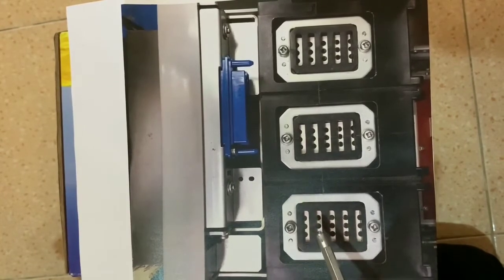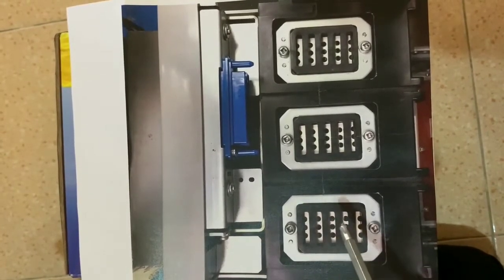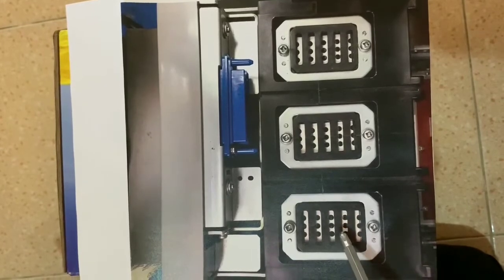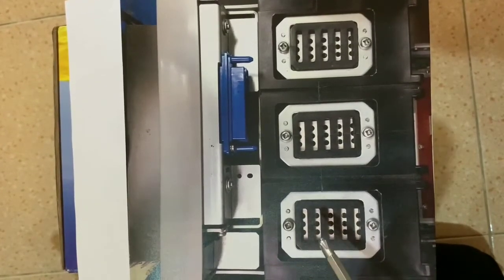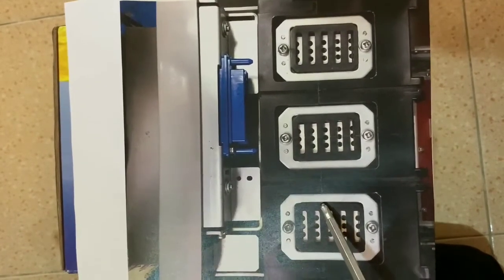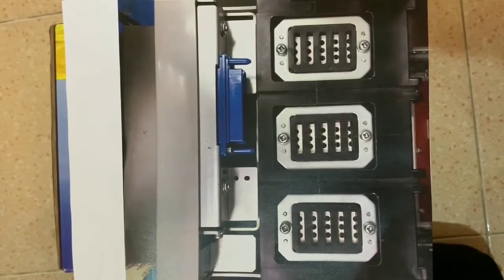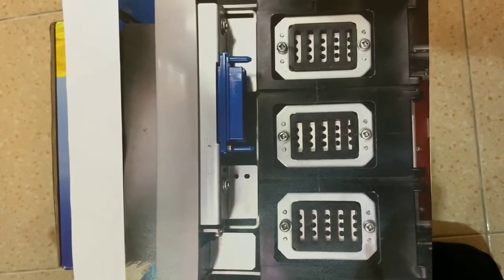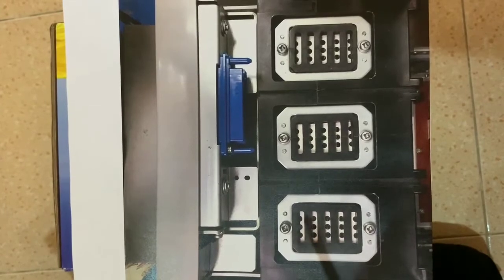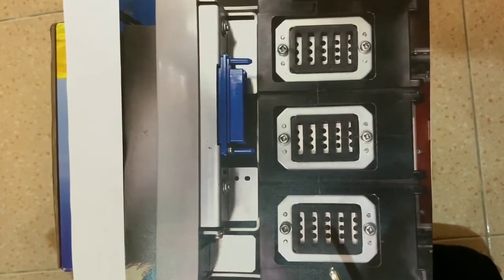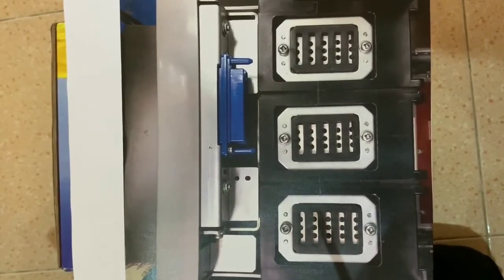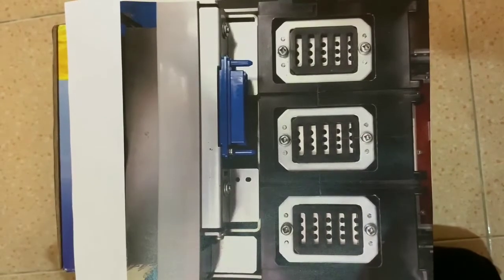Then we need to pull out the carbon paper, so we turn off the ACB, and we can see the result on the carbon paper. The main reason we do the arcing contact flatten test is to show how good the contact is between the moving contact and stationary contact. So that's all from me.